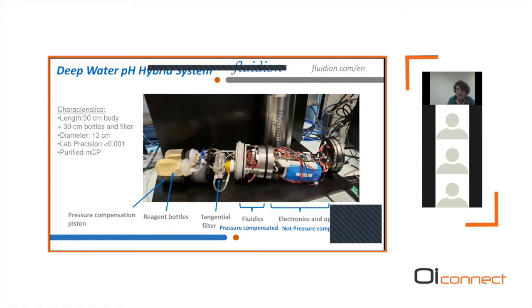the pump head. And here, this is the inside of the housing, which is divided into two compartments. This first compartment is for the fluidics. It's oil-filled and pressure compensated. That's where you have all the valves and the mixing of the reagent and the optical cell for the measurement. And here in the second compartment, it's not pressure compensated, and that's where you have the rest of the electronics and the optics. The advantage of this approach is that you can have some fairly sensitive optics and electronics, such as here, this multi-wavelength spectrometer, which enables moving to other parameters in future designs.